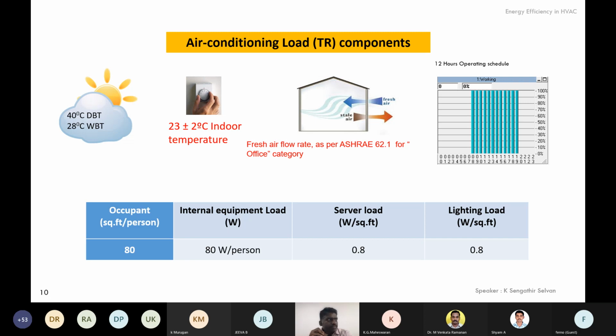And for electrical rooms or for machine halls in a thermal plant, the minimum fresh air shall be allowed inside, so that we are maintaining some positive pressure inside those critical rooms, and so that we avoid ingression of dust and other unwanted particles inside these critical rooms. And now for all these calculations, we have considered 12 hours of operating schedule. And again, the number of people are taken from general National Building Code standards.